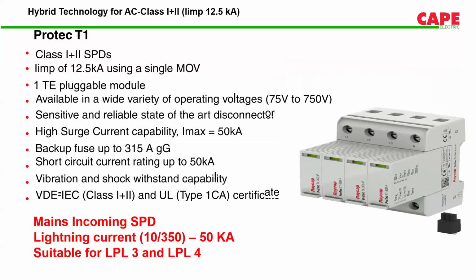These are class 1 SPDs which are TOV safe fail. As I told earlier, the standard has given two options for SPD: SPD can be TOV withstand or SPD can be TOV safe fail. TOV withstand SPDs were the T1 S series SPDs and HS series SPDs, which I have told you about just now. Now we have TOV safe fail SPDs called T1 SPDs.